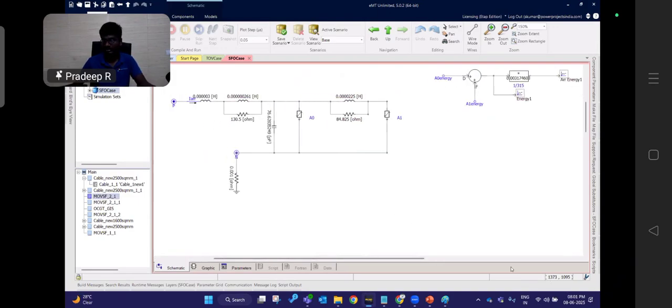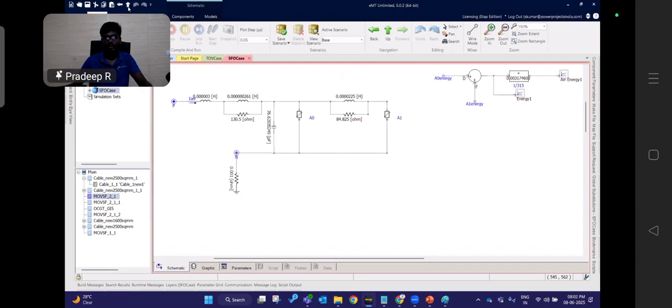Right? Not in this session as of now, due to time constraint. So this is known as the frequency dependent model of my surge arrestor. Why am I modeling the surge arrestor in such a detailed manner? Because I have to capture the frequency dependent oscillations. Why? Because during these cases my frequency will also get disturbed during switching as well as lightning events. Because the occurrence time is very low, and when the time is low, we know that the frequency will be very much higher. So during this case, to observe the frequency dependent behavior, I am going to model the surge arrestor like this.